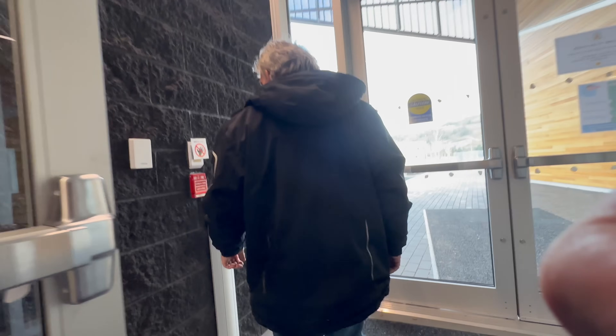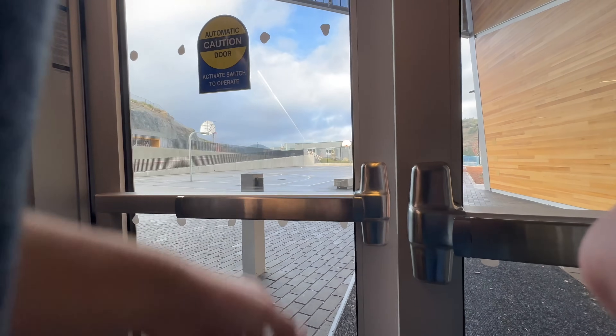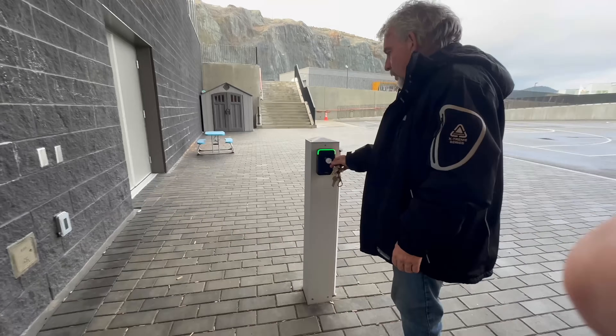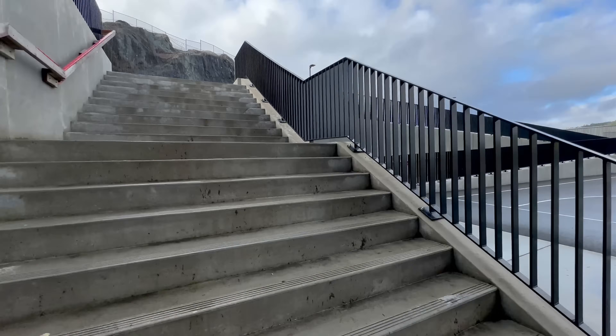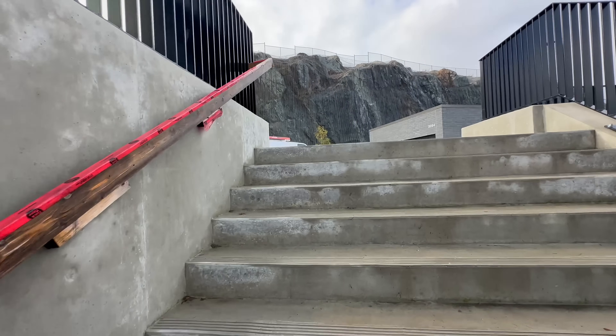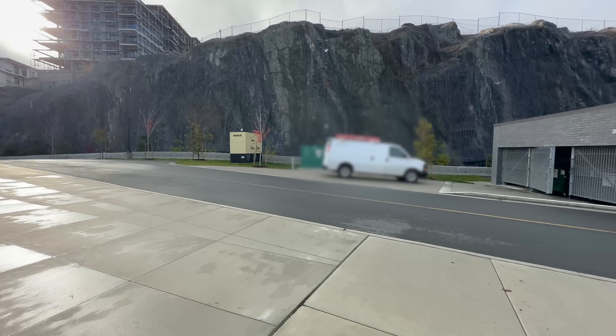The handicap opener works but the panic hardware doesn't open, which is useless. These are trying to open but the panic hardware's not engaging — that is pretty stupid. Exterior lighting is kept on; the wall packs are there. You need the fob to access — scan the fob. So this school, the central plant, and the middle school over there are all fed from the same one 250 kW generator right here, that keeps all the lighting, life safety, and all that sort of stuff running.